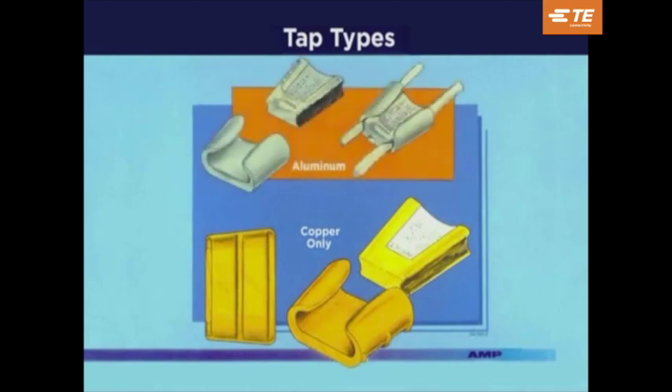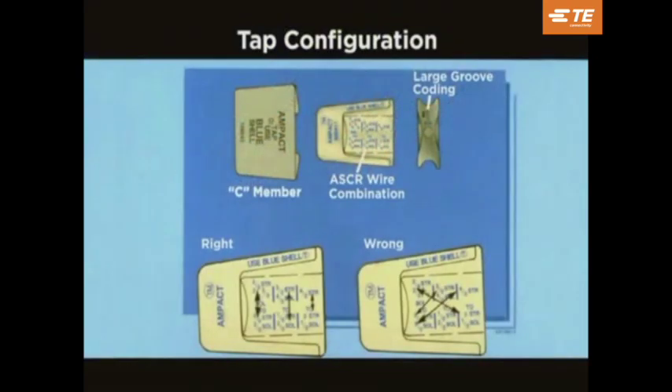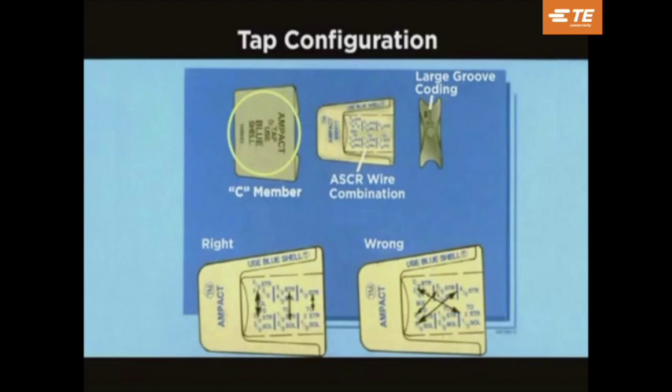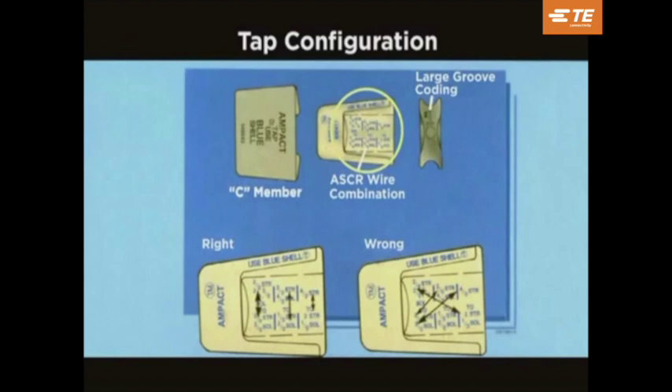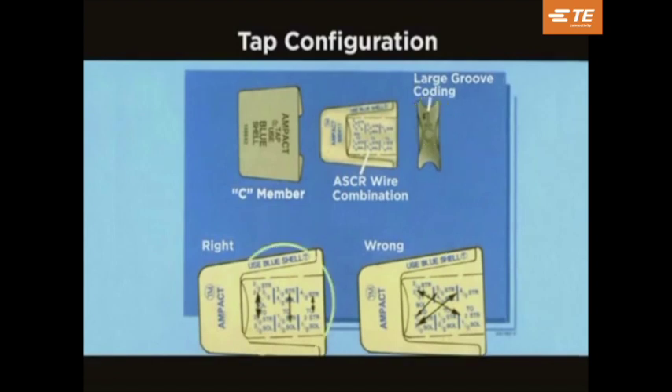Both types are available to cover a wide range of wire sizes. The aluminum TAPs can be used on various types of wires including duplex, triplex, and ACSR. Listed on the back of the C-member is the correct color-coded shell to be used. Listed on the tapered wedge are the various wire sizes to accommodate the large variety of wire combinations. The large wire groove is also coded. Markings are printed to be read up and down the column, not diagonally.